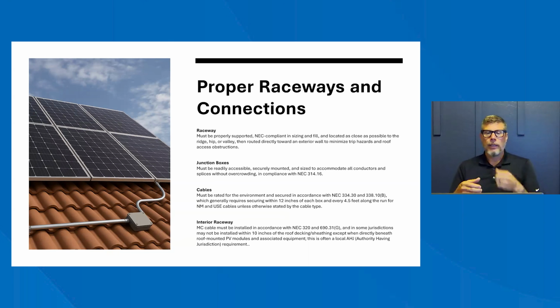So let's start with the raceway. These are rigid, flexible conduits, they're protecting all the wires. You'll see them on the roof. You're going to see them through the attic. If it's on the roof, you want to make sure they're securely mounted, that they're routed cleanly. Typically, it's going to be along the ridge. It's going to be down the hip, or it might be through a valley. Then you want to make sure that it goes towards the exterior wall in the most direct fashion to get to the inverter. This is going to help keep the installation tidy and minimizes trip hazards for anybody that's having to walk the roof, such as a roofer, the solar technician, or a firefighter who had to go up there and vent the roof for any reason.